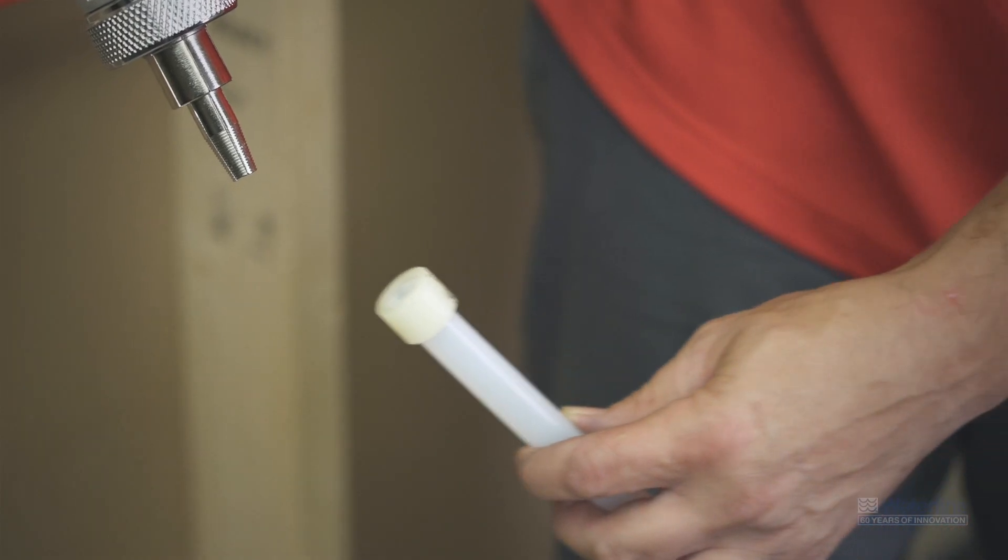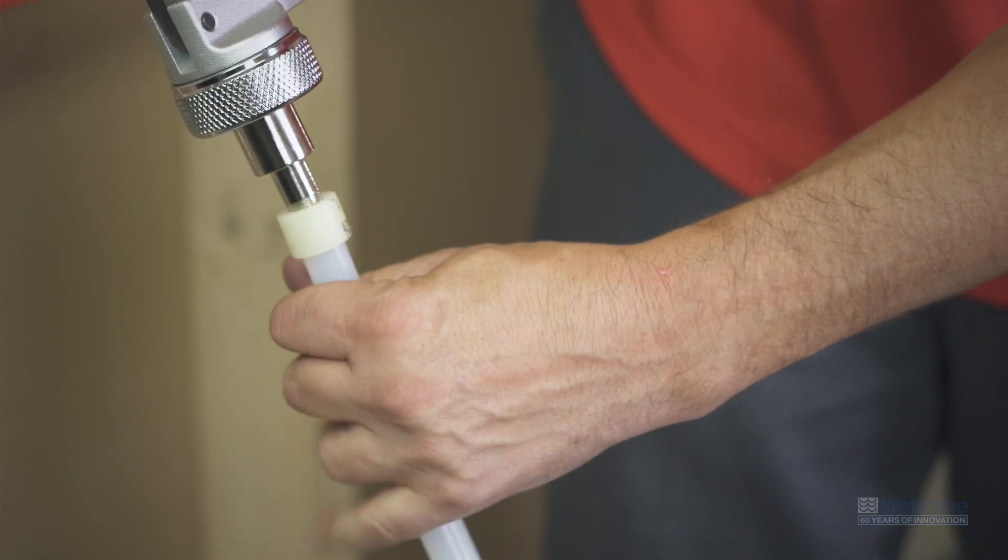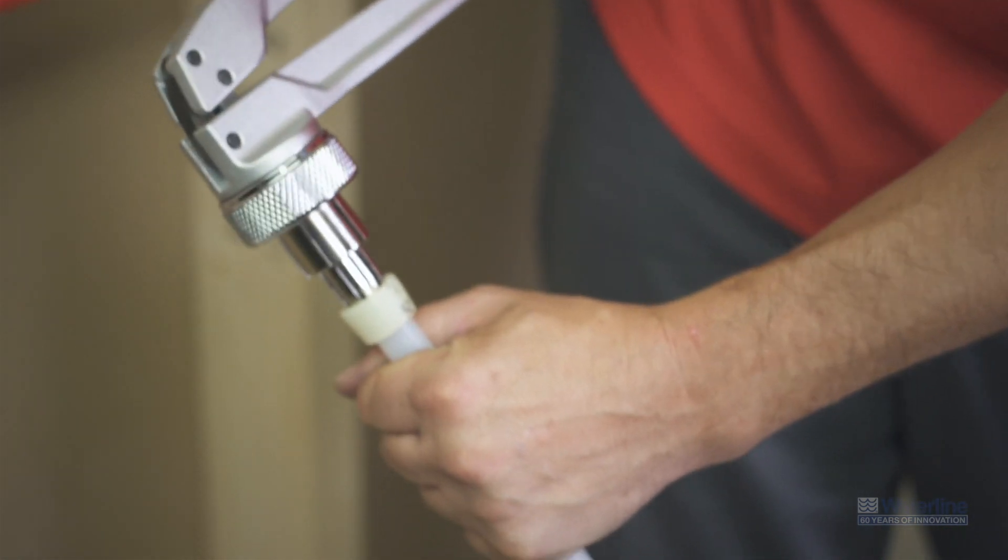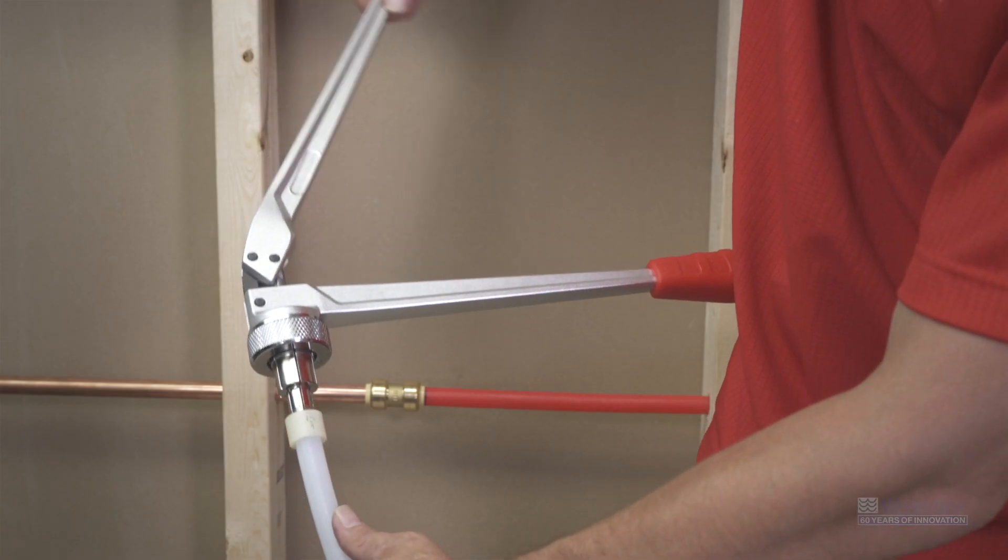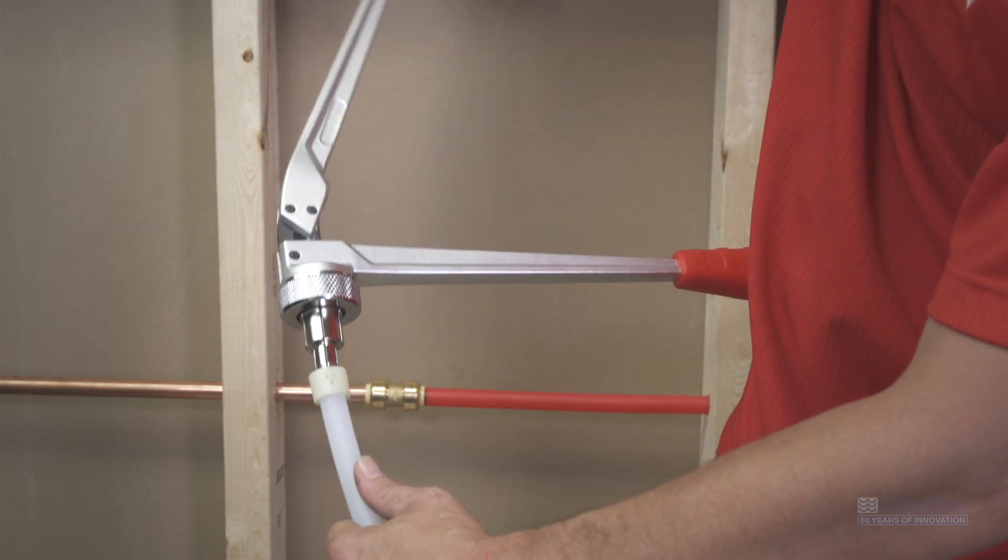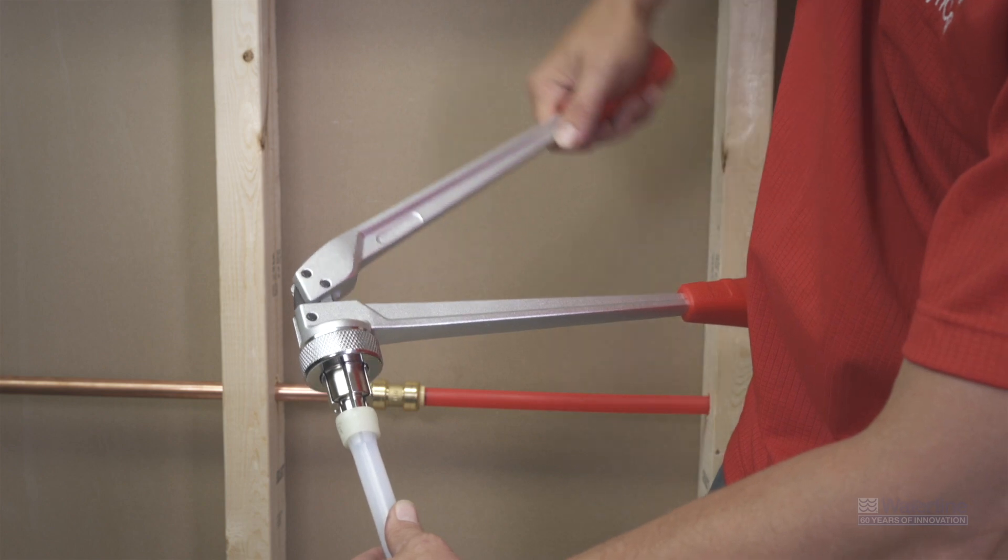Now attach an expander head that corresponds with the size of tubing onto the expansion tool. If you're using a ColdX manual expansion tool, insert the head onto the tubing with the handles of the tool completely open. Squeeze the handles together and repeat each time, rotating the pipe 90 degrees and inserting the head further into the pipe.